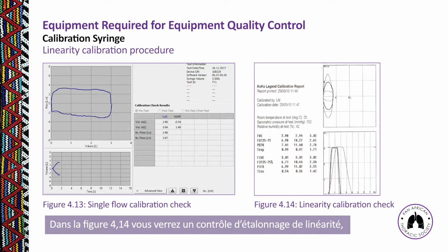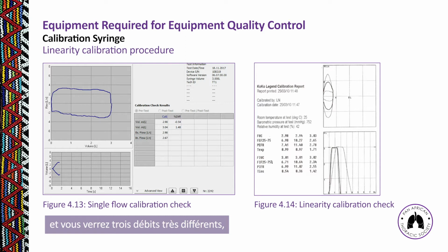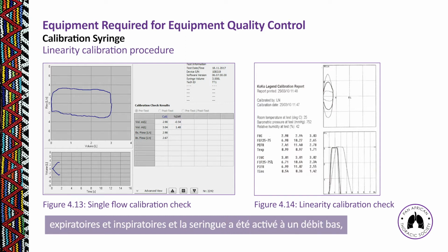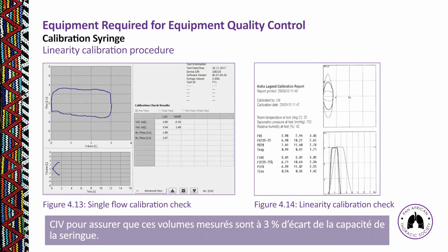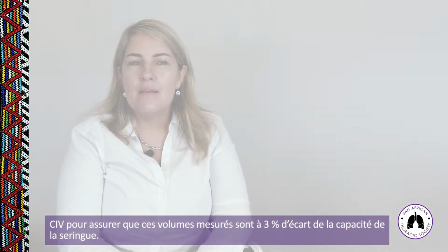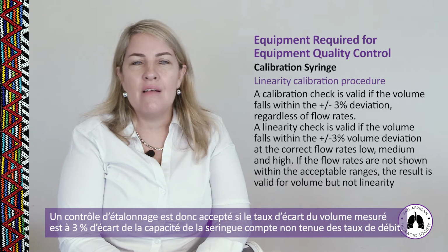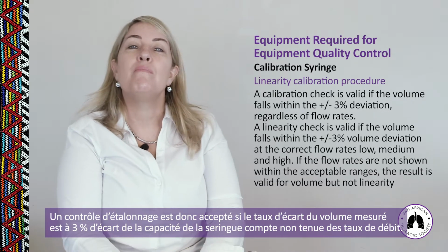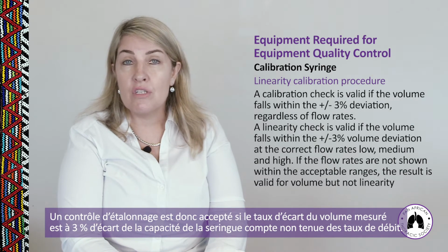In figure 4.14, you will see a linearity calibration check. There you will see 3 very distinct flow rates, expiratory and inspiratory, and the syringe has been moved at low flow, at medium flow, and at high flow. And then we look at the FVC measurements and the FIVC measurements to ensure that those are within 3% of the syringe volume itself. So a calibration check is valid if the volume falls within plus or minus 3% deviation of the syringe volume, regardless of the flow rates.